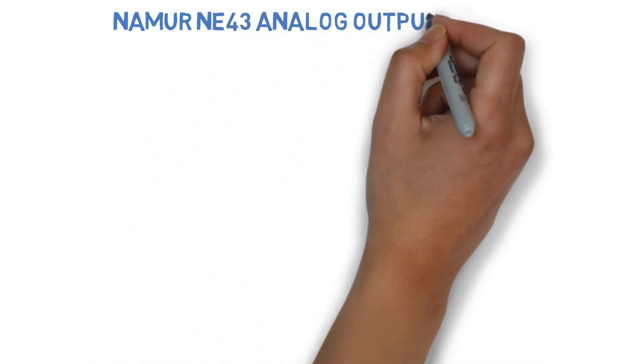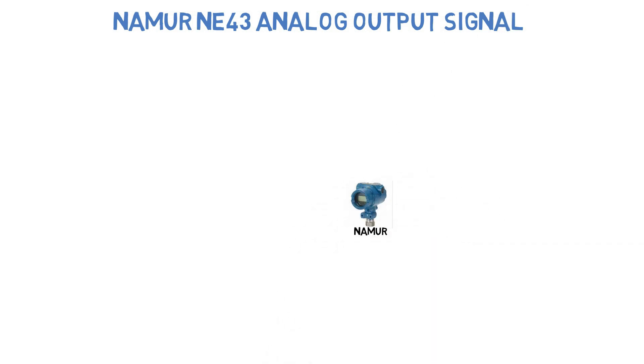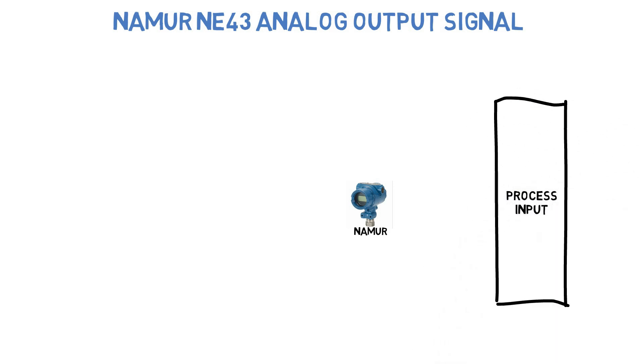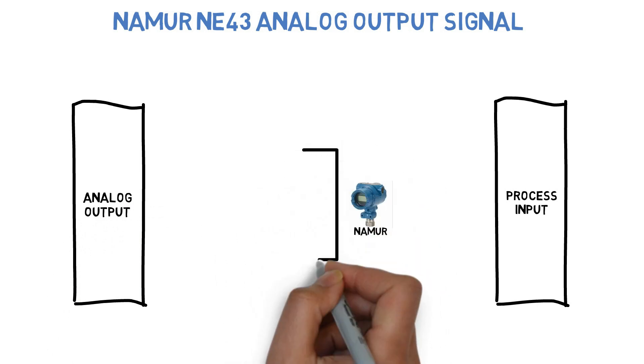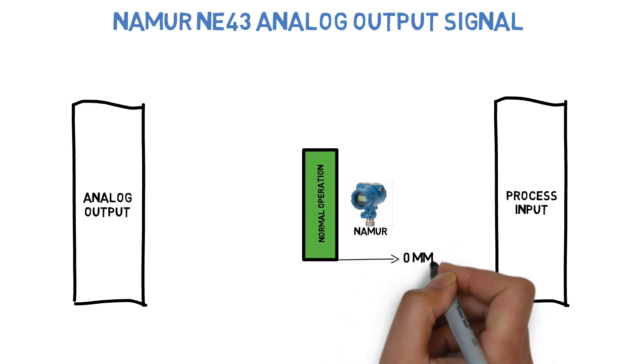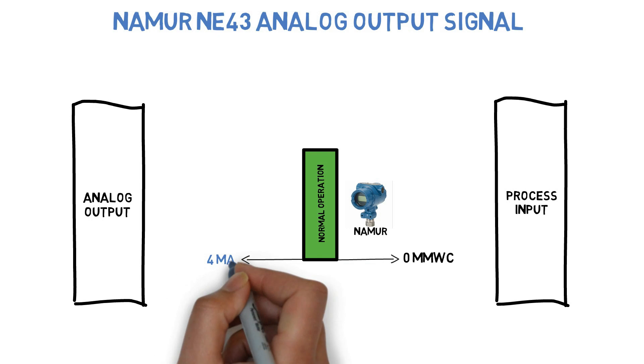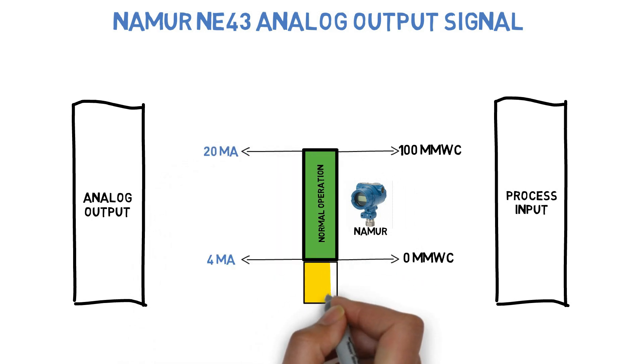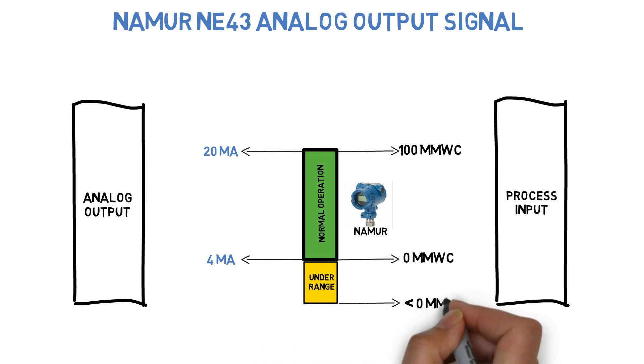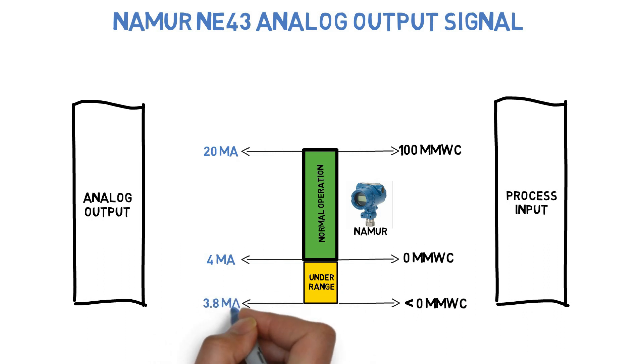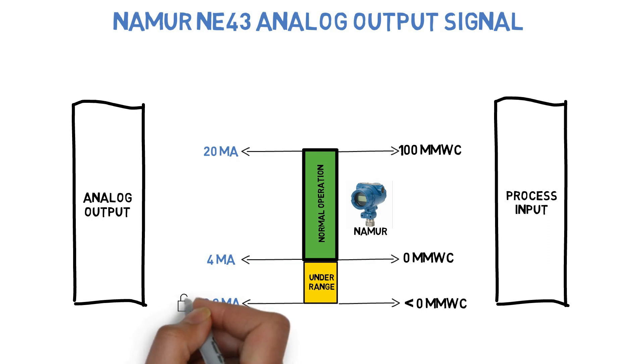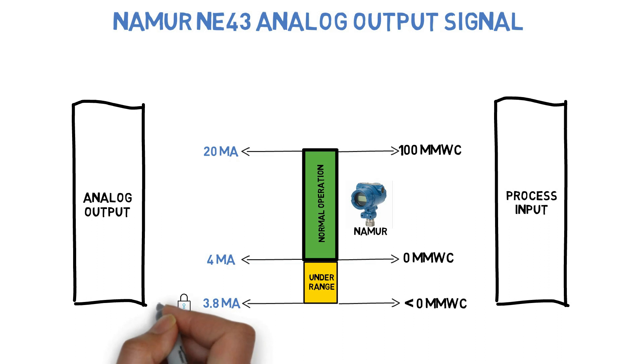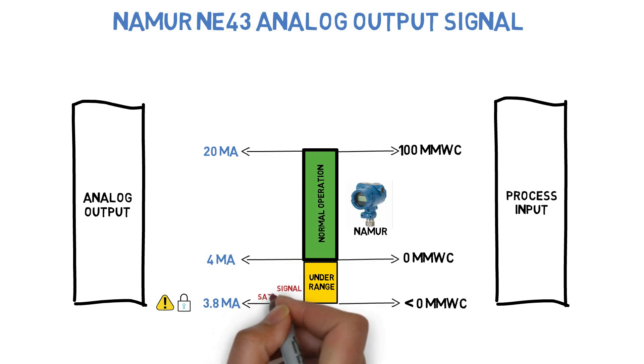Now for the NAMUR NE43 Analog Output Signal. During normal operation, the transmitter analog output shall be between 4 to 20 mA. If the process input falls below the lower range value of the transmitter, the analog output also reduces between 4 and 3.8 mA. If the process input exceeds the lower range value, the analog output holds at 3.8 mA, warning the control unit of an out-of-range event. This out-of-range signal is referred to as signal saturation.